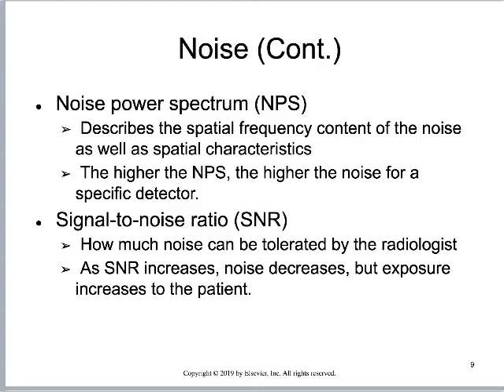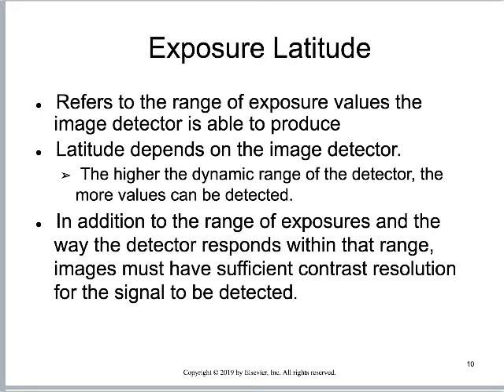That's what happens in our digital systems. If we can't get rid of the noise — backscatter radiation is real, background radiation is real — we can't eliminate it. These detectors are sensitive to it. So we have to increase patient dose to shout over the noise. Fortunately, digital systems are prepared to hear even the shouting over the noise. That's what we're talking about when we say digital systems have an exposure latitude benefit.